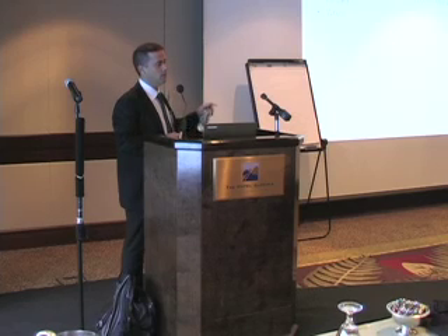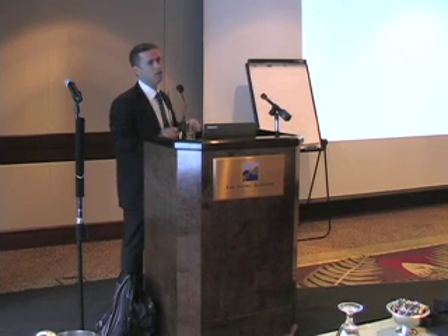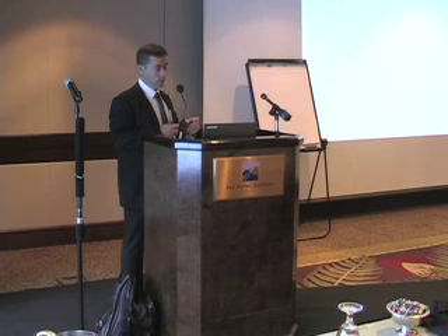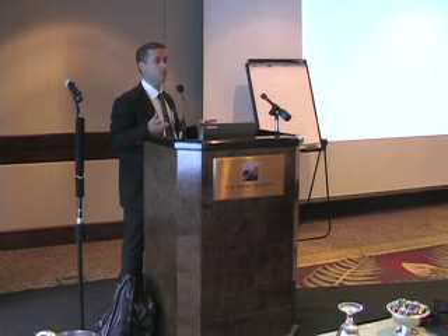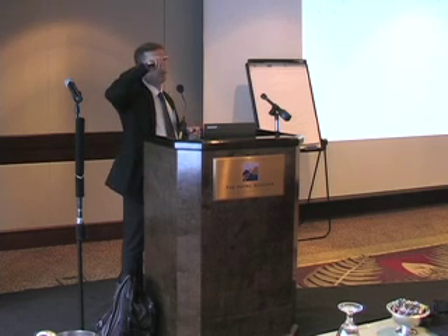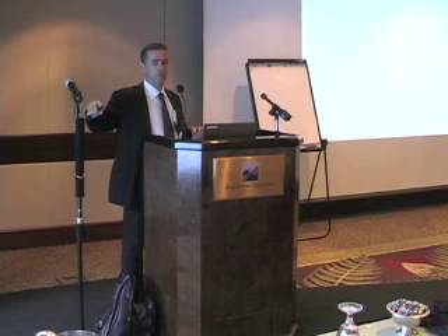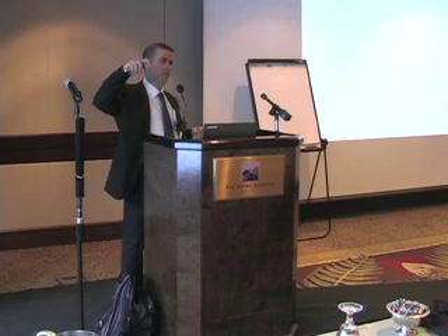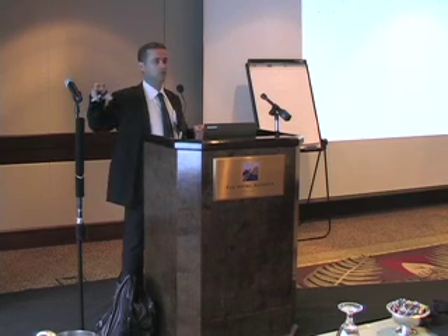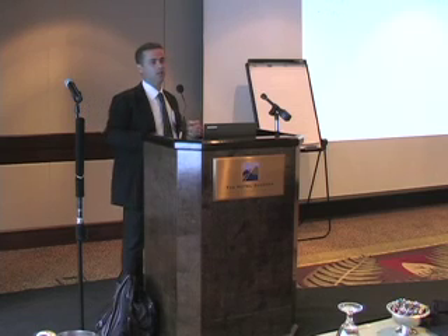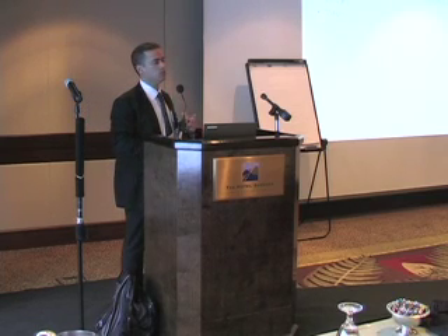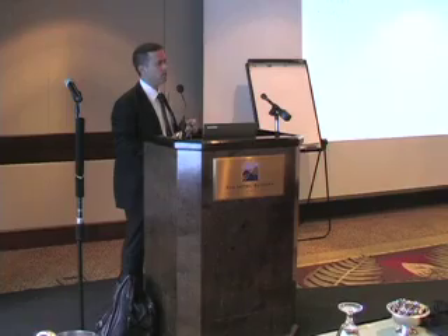I can talk to you later about the machine we do. It can do 6 times its rated current for 1.5 seconds. So if that protection is fast enough to operate in that time, then that's good. But if there's a sequence of events that needs to happen to trip feeders off after 1 second, another one after 2 seconds, etc., to try and keep the town on, then that may not be appropriate technology to use, and synchronous compensators are much smarter.